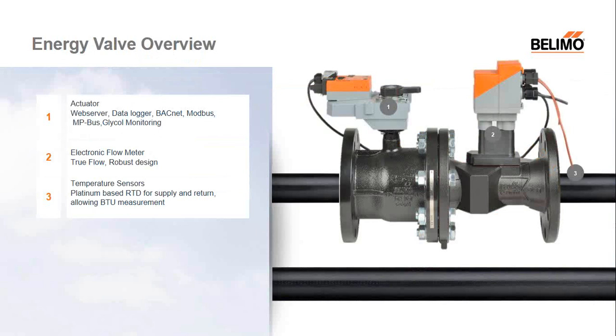So this not only is a control valve, it also can be used as a BTU meter as well. So it's another feature integrated directly into the Belimo Energy Valve.